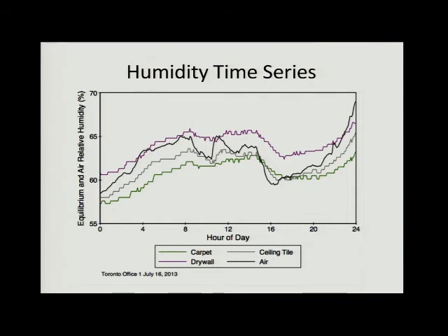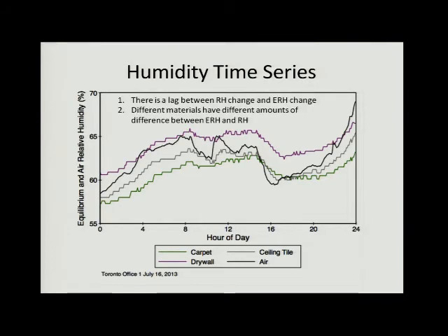And there are a couple of things that I want you to note. First of all, there's a lag between when the relative humidity changes and when the equilibrium relative humidity changes, and that lag is material specific and typically varies over the course of hours. The second comment I want to make here, and the more important one, is that there is really a big difference between relative humidity and equilibrium relative humidity for some materials. So this is not a particularly extreme day, but note that you can already see that the drywall is looking different from the other materials, and certainly from the air in terms of that lag.